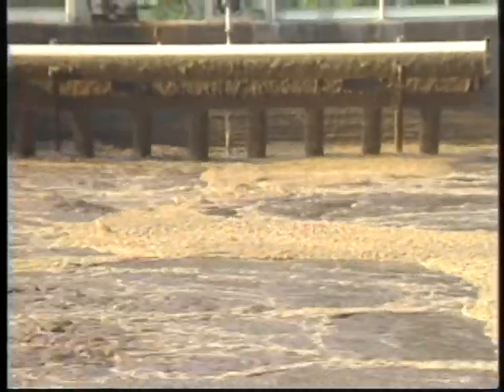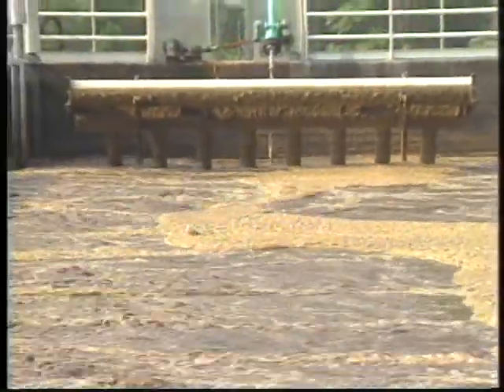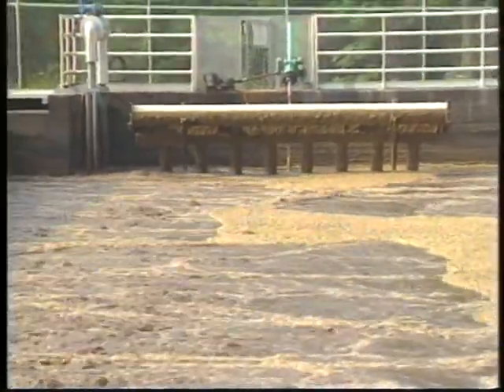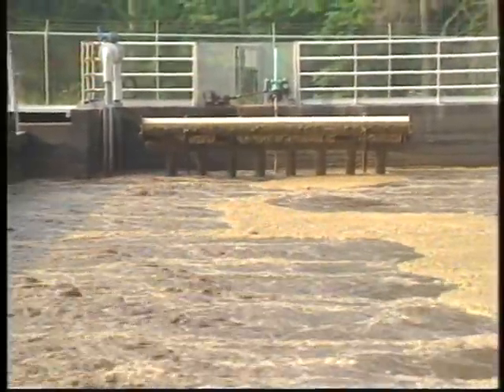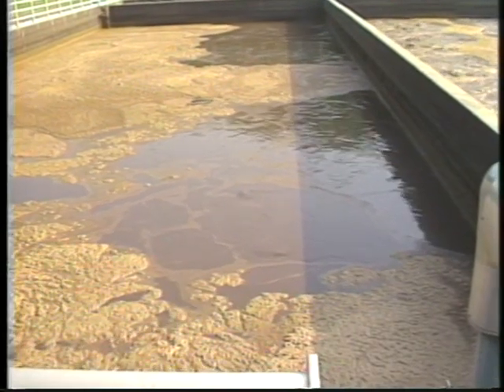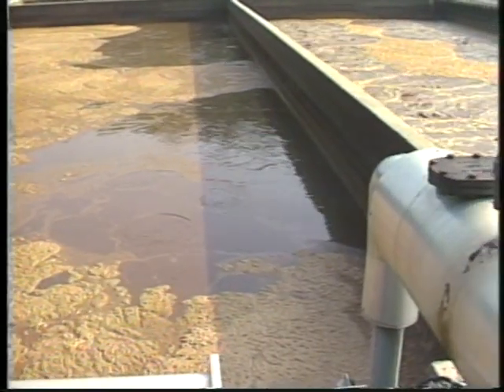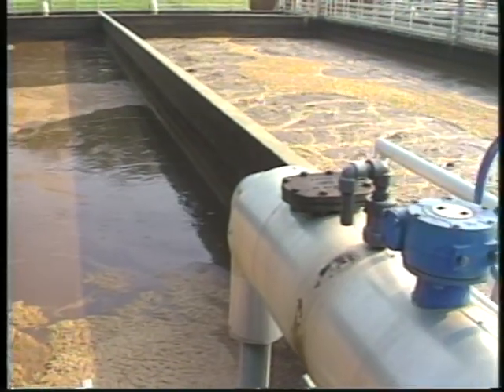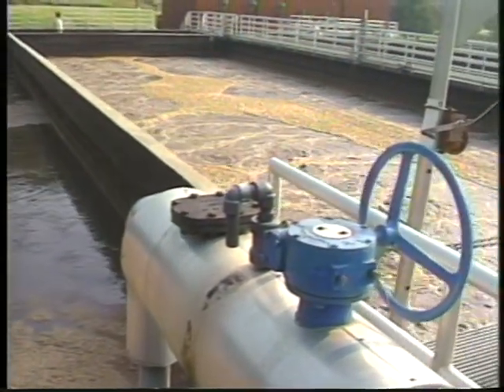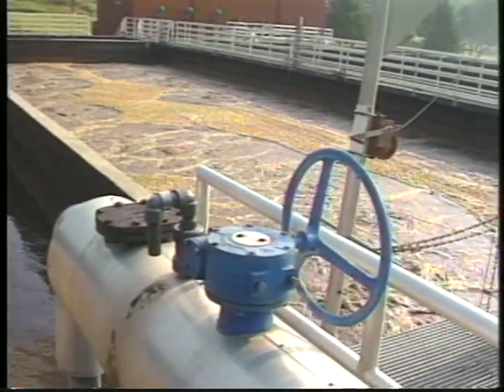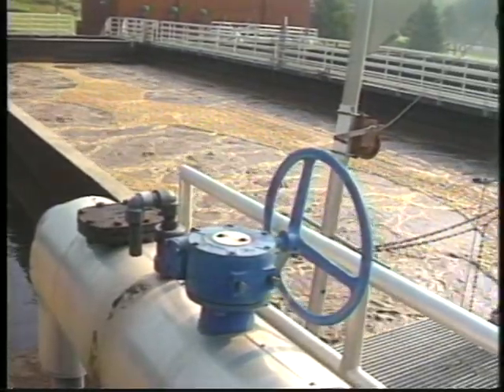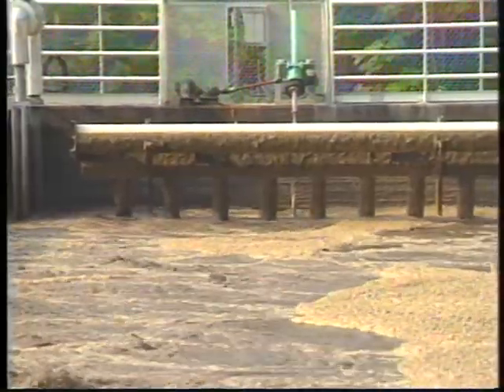mixed liquor. The sequential batch reactor is configured differently from the other processes we have looked at. In the sequential batch process, everything happens in the same tank. There is no separate final clarifier. There are usually a series of several tanks at a sequential batch type of plant, with each tank at a different stage of treatment. There are four basic sequences to a batch reactor. The filling mode, where the raw wastewater enters the aeration tank.